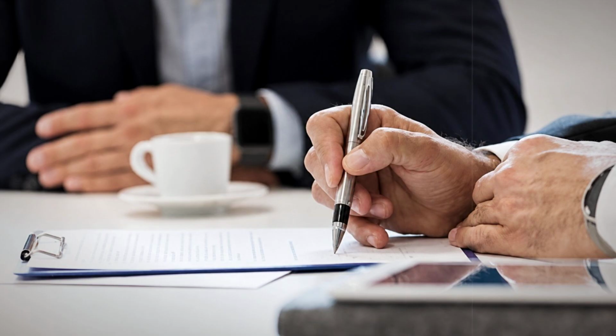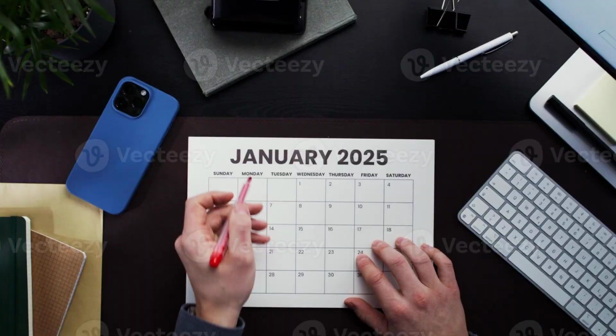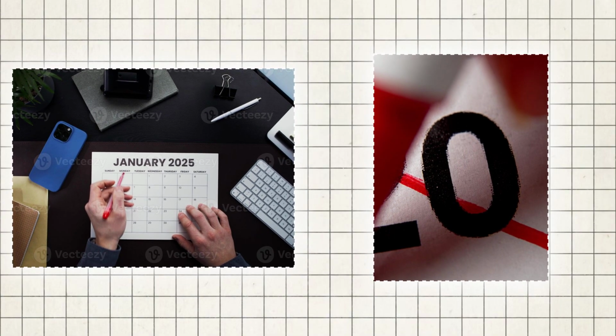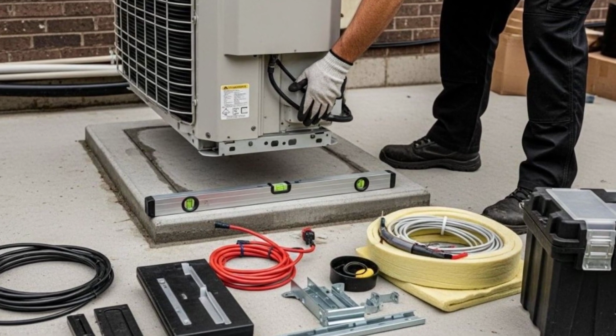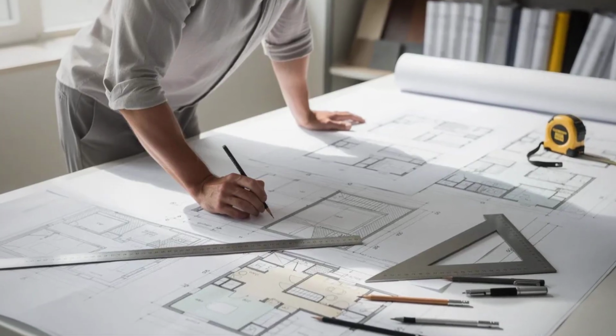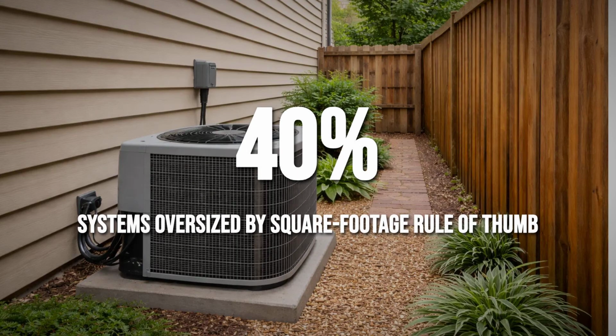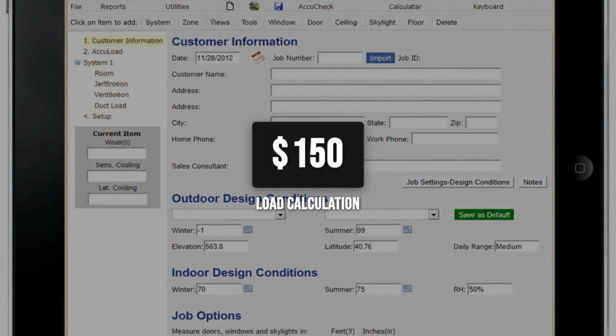Then the financing layer. A consumer research nonprofit documented lease programs marketed like loans. One retired firefighter, a $22,000 system, 10 years of payments, no ownership at the end. And underneath it sits sizing. Building science analysis shows the square footage rule of thumb oversizes systems by 20 to 40%. A proper load calculation costs $150 to $500.